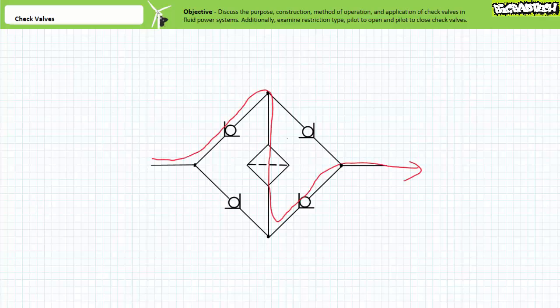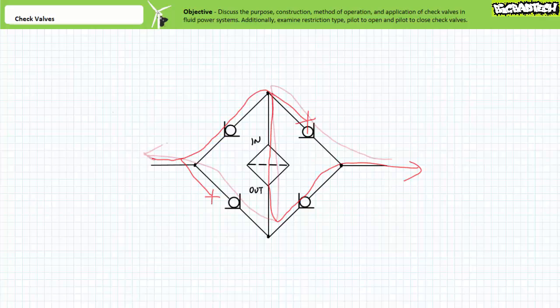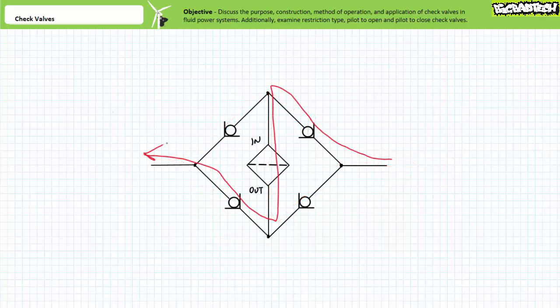These check valves permit free flow and these check valves are blocked. Fluid is therefore routed in to out, top to bottom. When flow reverses its direction, these check valves permit free flow and these check valves are blocked. Again, fluid flow is routed in to out, top to bottom as intended. Despite the bidirectional nature of fluid, this special arrangement of four check valves ensures unidirectional flow through the filter.